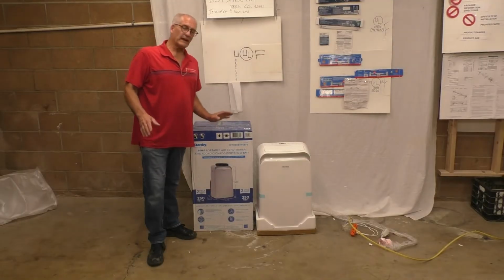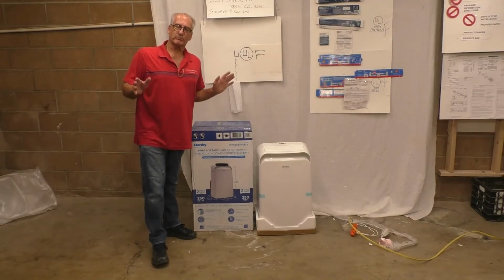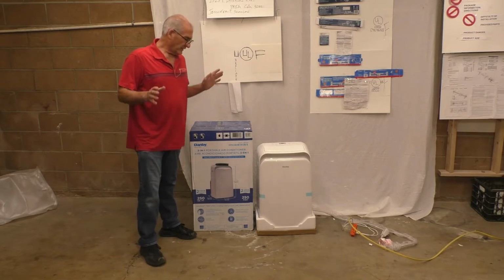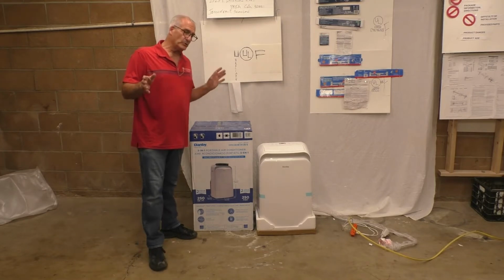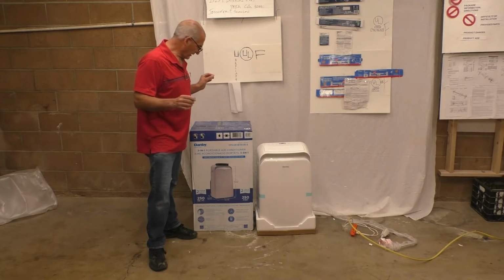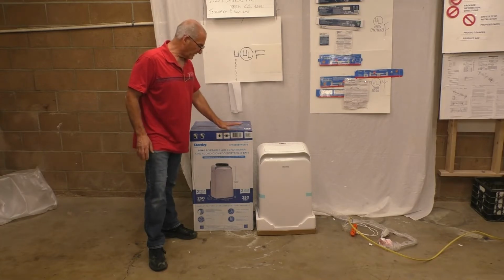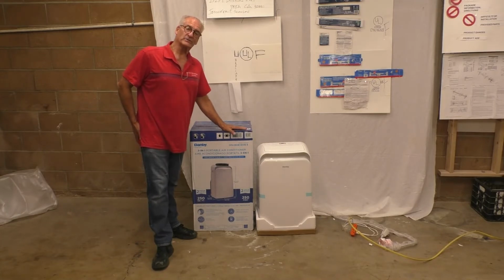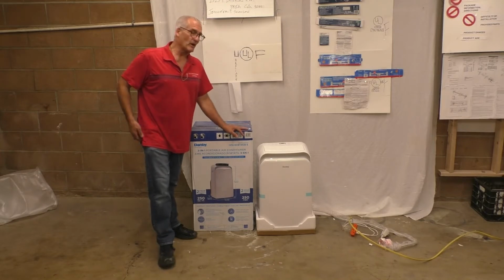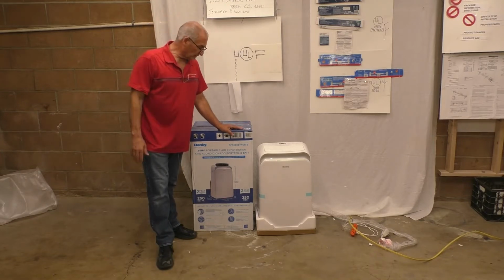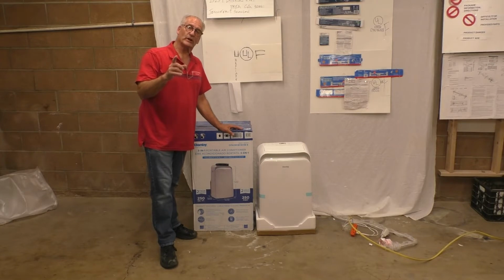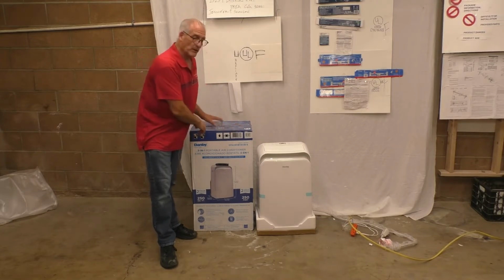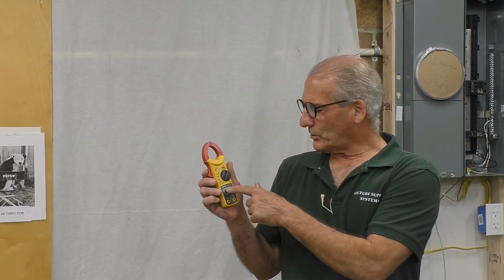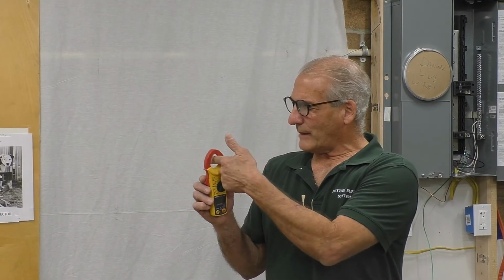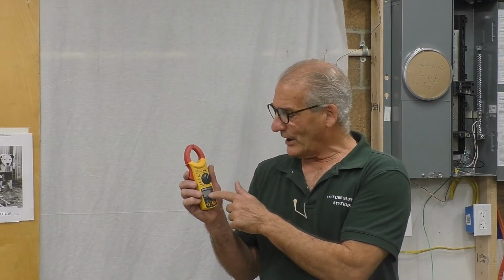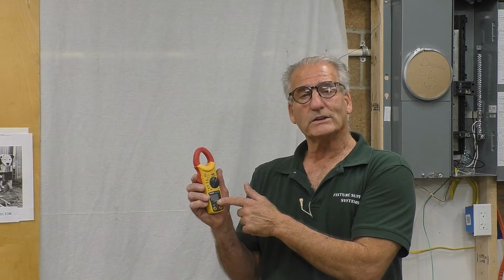So being that I have a lot of experience in the problems in houses, the number one problem, like I said, is what you use to plug in the sockets. So we're going to have to test this out because it doesn't say anything about what kind of current you take. A 115 volt, 15 amp outlet, I know it's not good enough, but we're going to check it out anyway. We're going to do a test on this thing because they won't show you on the box. This here is an amp probe. I'm going to wrap it around a wire to read out the current going through the line.